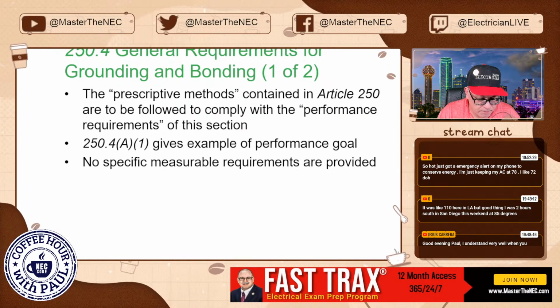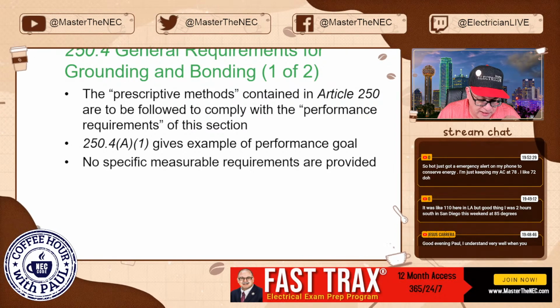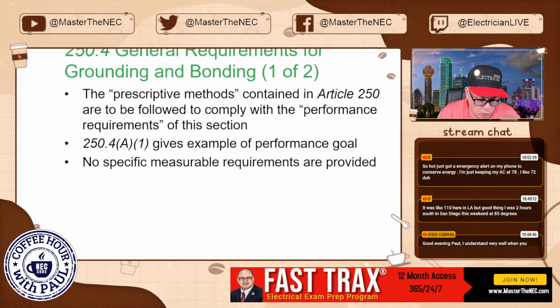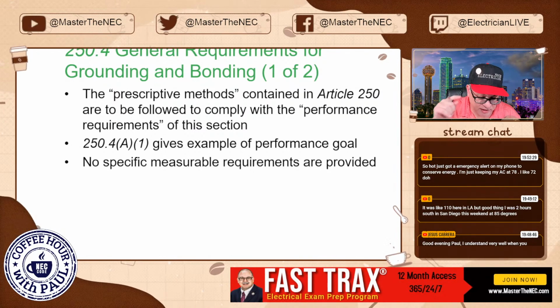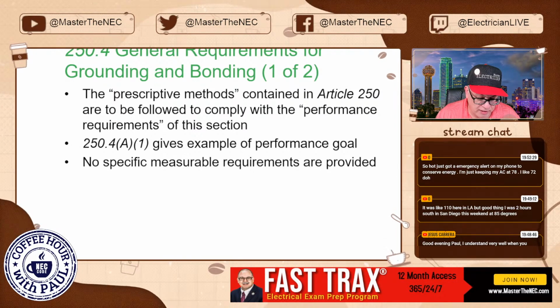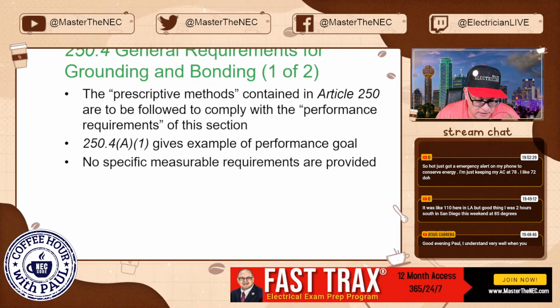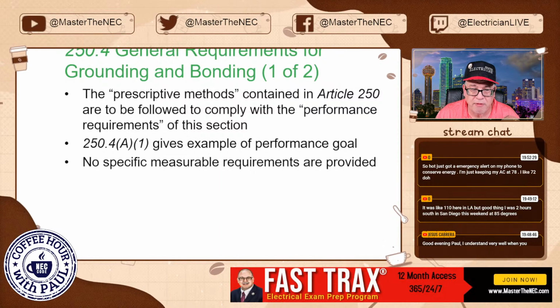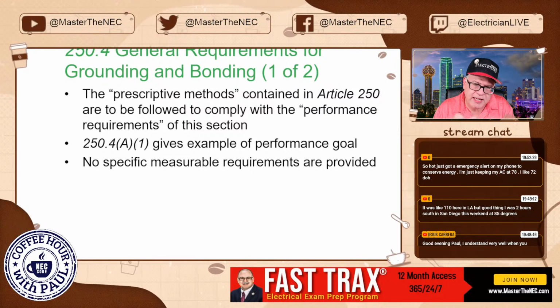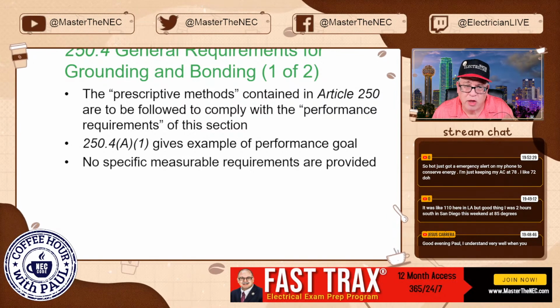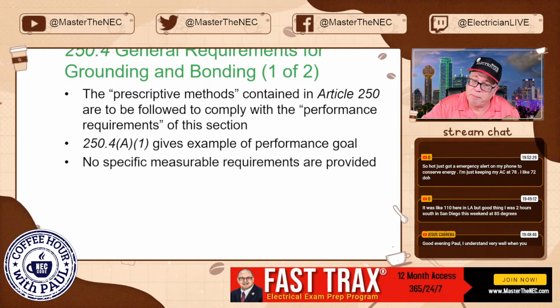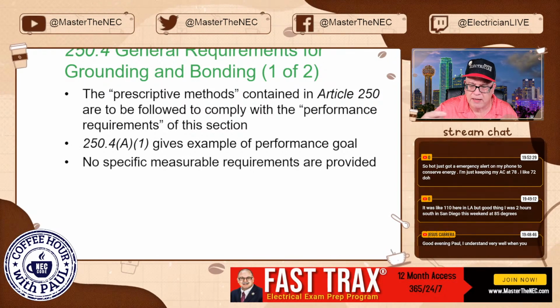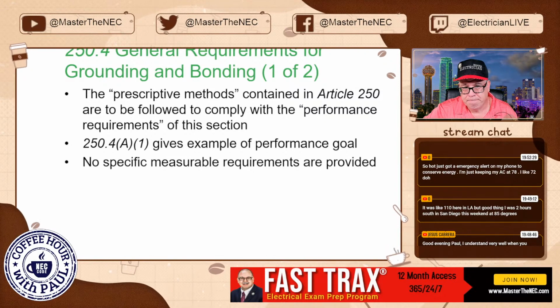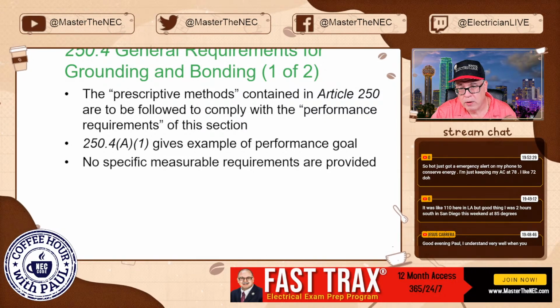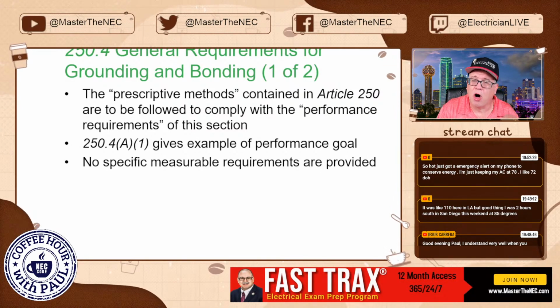Okay, so what does that say? Well, 250.4(A)(1) requires grounded electrical systems to be connected to earth in a manner that will limit the voltage imposed by lightning, line surges, or unintentional contact with higher voltage lines. It also states a purpose of the grounding connection is to stabilize the system voltage to earth during normal operation. So if you do what the code tells you to do, then you're going to get the performance that's desired and explained in 250.4(A)(1). As you go through 250, it's going to tell you things you need to do. Those are called prescriptive methods, with a goal to meet the performance goal of Article 250.